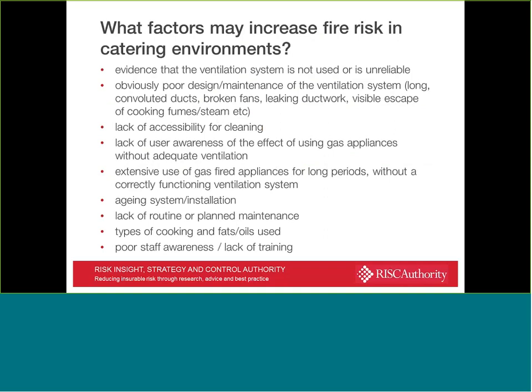There may be other factors that increase fire risk in catering establishments. For example, evidence that the system is not used or is unreliable, and these are the sorts of visual checks that we need to make when we're inspecting systems. Obviously, poor design and maintenance of the system, and we'll be talking a little bit about what constitutes good design in a few moments. So we may have long convoluted ducts, we may have broken fans, ductwork may leak, there may be visible escape of cooking fumes or steam from the process, for example.